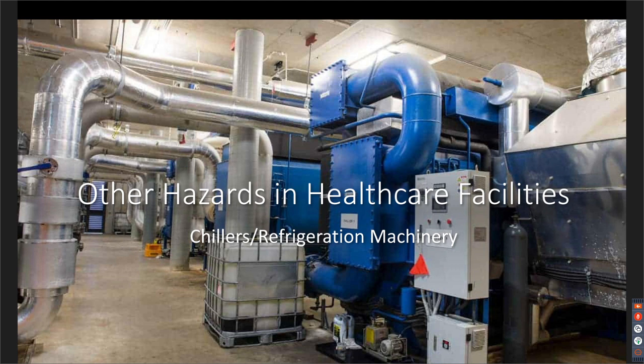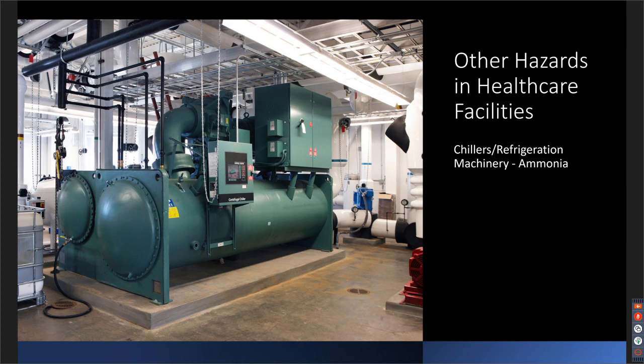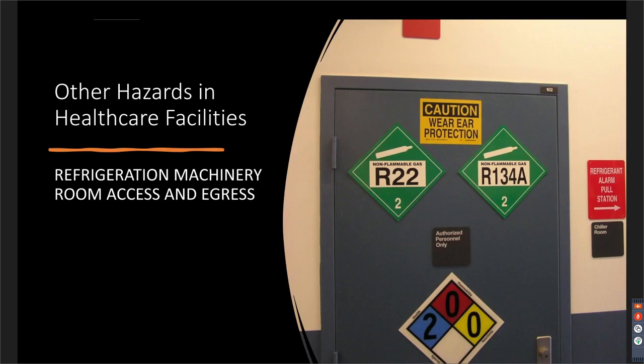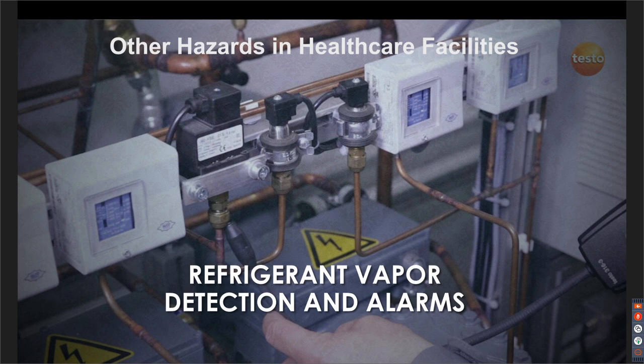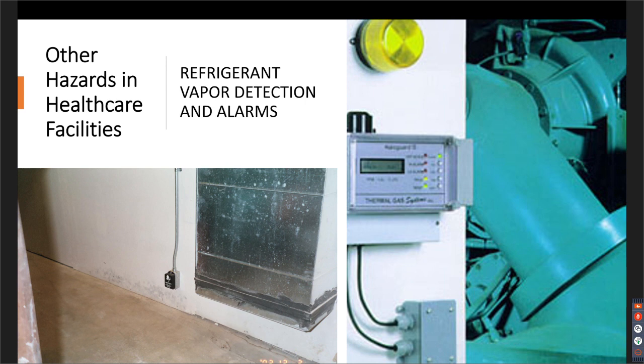Moving on to the other part of the central plant, how about chillers and refrigerators? Chillers in and of themselves aren't overly hazardous, although the refrigerant certainly can be, depending on which refrigerant is being used. With refrigerants that are hazardous or may result in a simple asphyxiant condition, vapor detection alarm systems are required in these facilities. These alarm systems are required to be located in such a place that it's likely to detect the refrigerant. So if the refrigerant is heavier than air, the sensors need to be down along the floor.